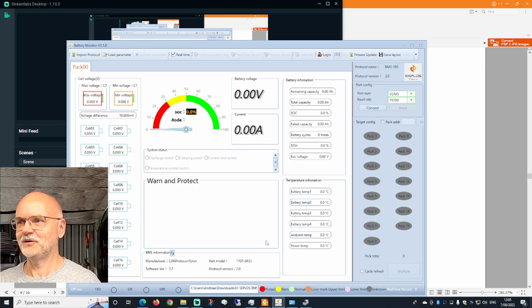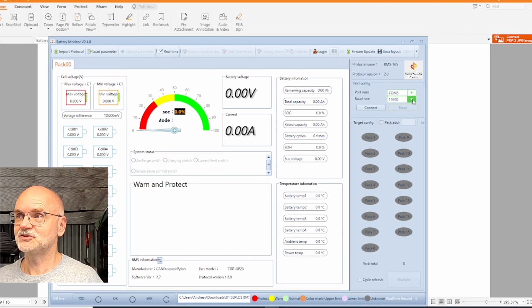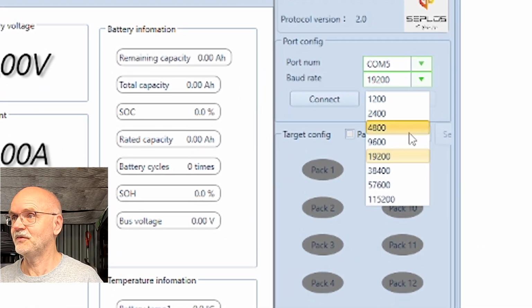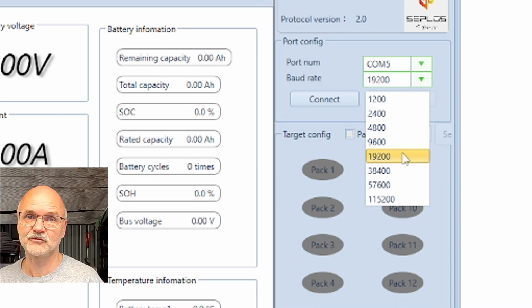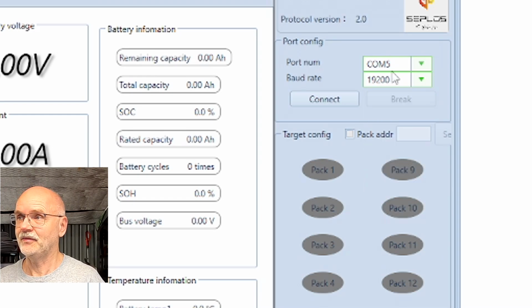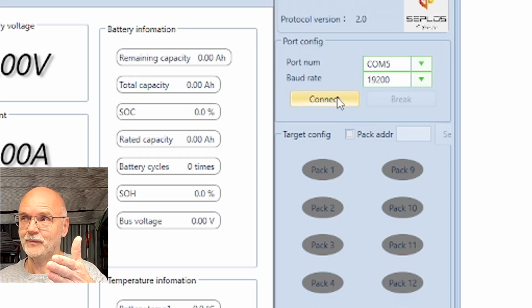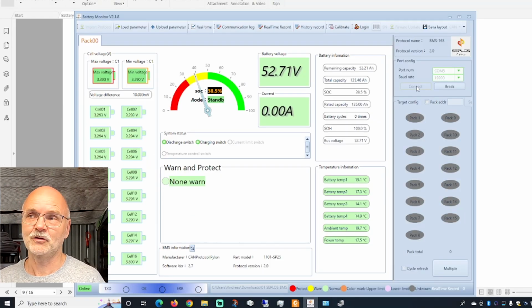Okay, I found it in the manual. What we have to do is change the baud rate from 9,600 to 19,200 apparently, then connect via COM5 - in my case, there's a different COM port on your computer. Then we click connect, and it connects to the BMS. We've got the overall voltage here, the amps, all the different cell voltages showing up, and this is the communication animation down here.